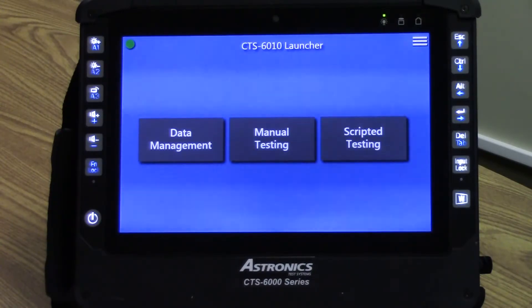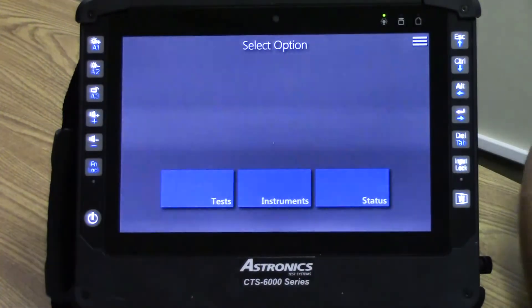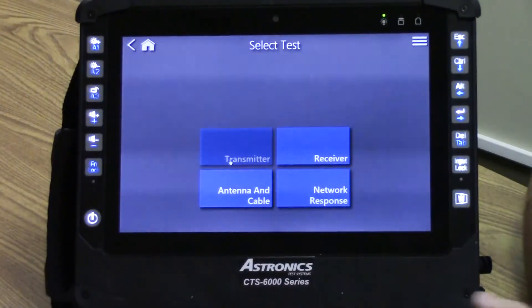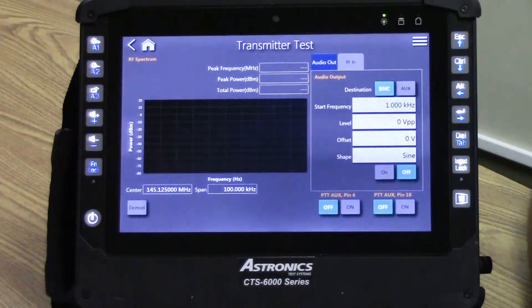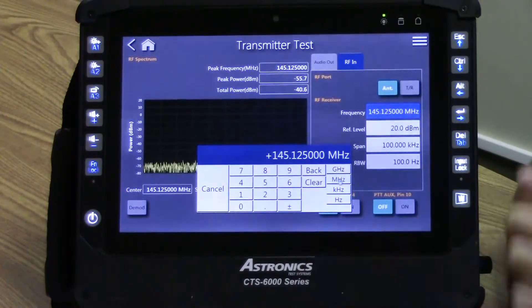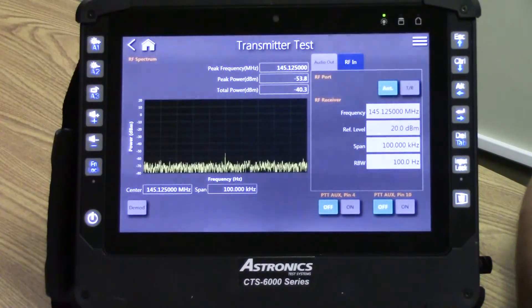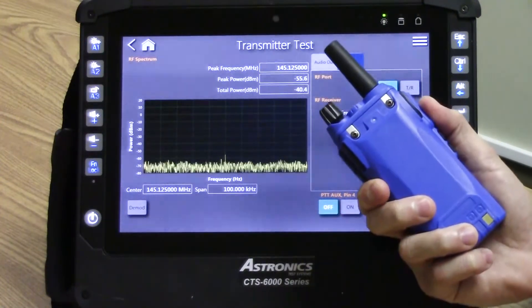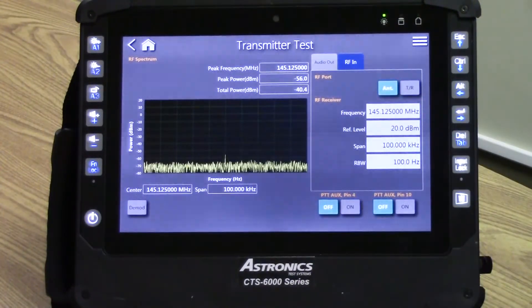Using the CTS 6010 is very easy to check that a radio is transmitting properly without a direct connection over the air. From the CTS 6010 launcher we'll enter manual testing, then select Tests, which enters our semi-automated mode. To test our UUT's transmitter we will select the transmitter test. Next, we will configure the CTS 6010's RF receiver to match the carrier frequency of the transmitter, and then we'll be able to visually see on the frequency spectrum when push-to-talk is enabled, showing that the radio is transmitting.